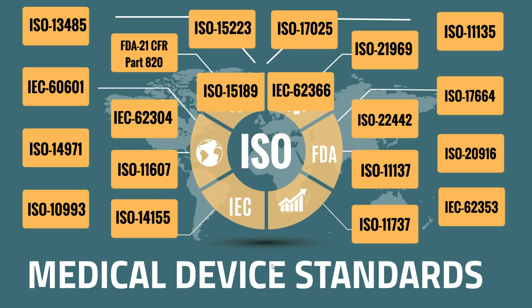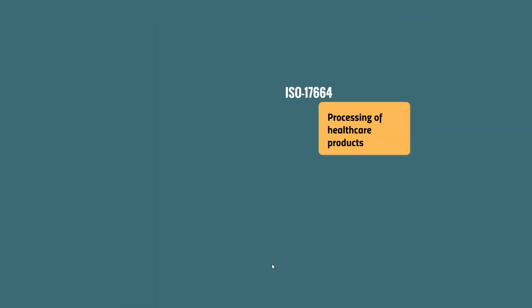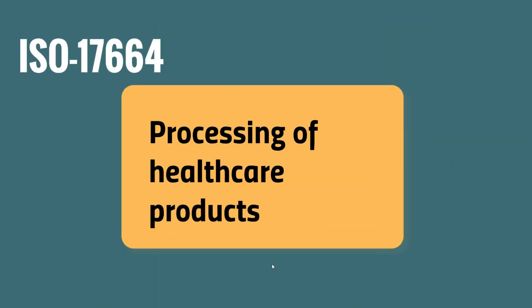18. ISO 17664 — this is the standard related to processing of health care products. This standard specifies the information to be provided by the medical device manufacturer on the processing of medical devices claimed to be re-sterilizable and medical devices intended to be sterilized by the processor.